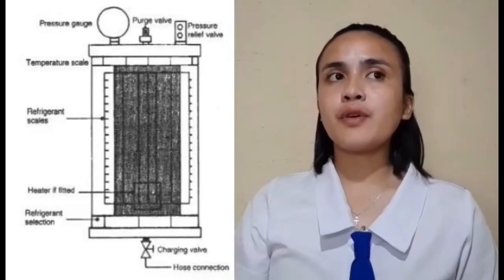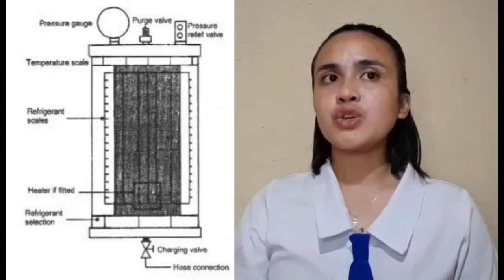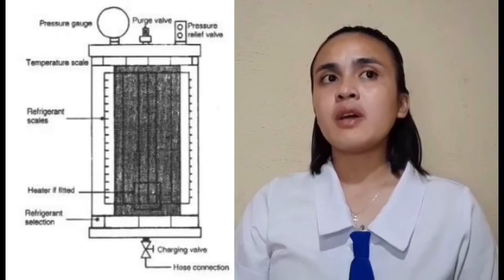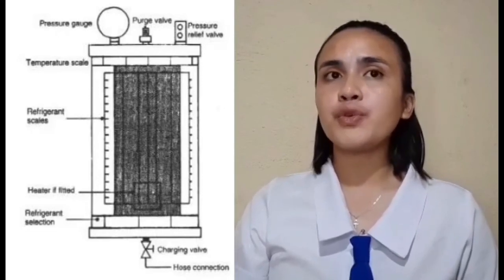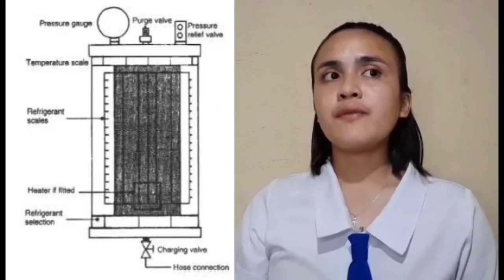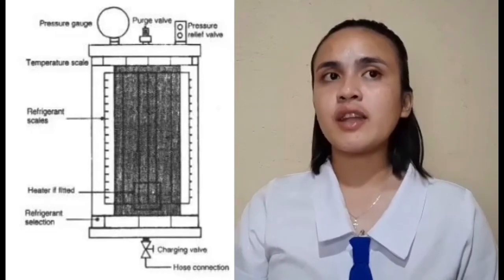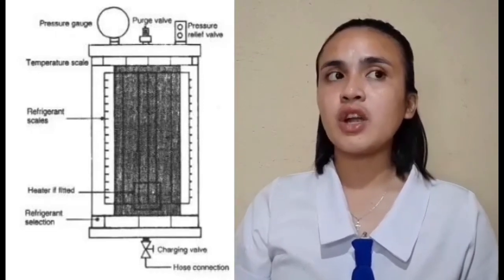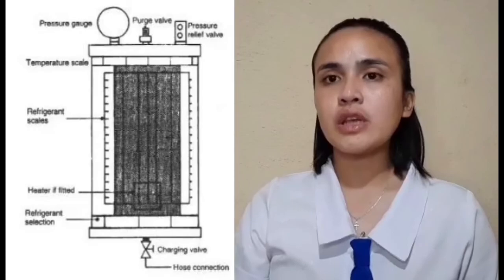Fitted to the top of the cylinder assembly are a pressure gauge, a purging valve which is normally a Schrader type, and, if a heater is incorporated, a pressure relief valve for the cylinder protection. At the base of the cylinder is a charging valve and hose connection. So let's go to the filling of the cylinder.